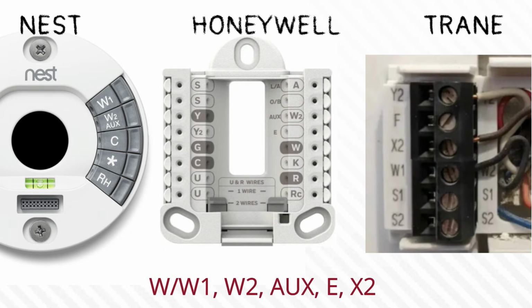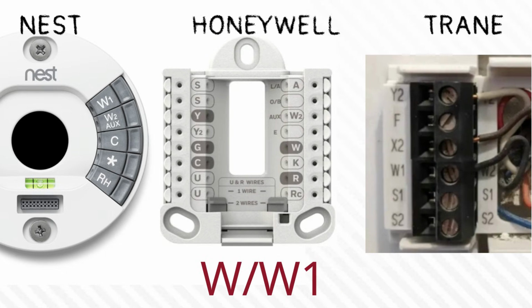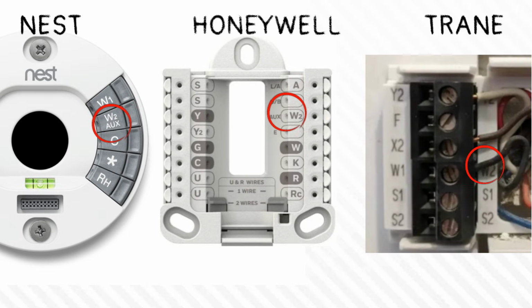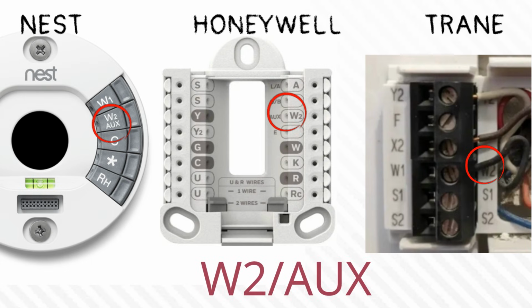A lot of manufacturers kind of jumble up how they handle all the heating terminals in their thermostats. You'll see a lot of different combinations out there. WW1 is usually the least confusing for most people because this is the only one that's really uniform on most thermostats. This is basically just your straight up heat mode for furnaces, hydronic boilers, steam boilers, and so on. W2 and auxiliary are often interchangeable, kind of like the OB terminals for a reversing valve, because the W2 and auxiliary can often activate the same source of heat. They just do it in different circumstances.